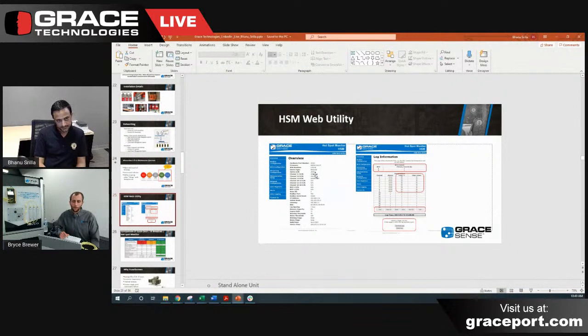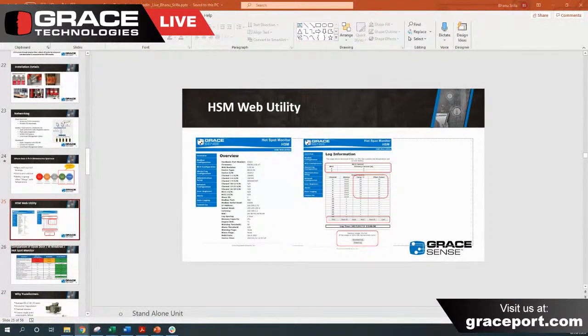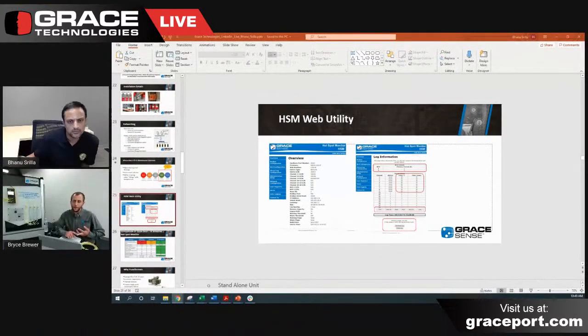Yeah, absolutely. So the way you would set up one of these devices is you can plug in right from your computer using an Ethernet cable and bring up the HSM web utility you're seeing there. The web utility allows you to put in IP addresses - that's where you would set that up. So it's kind of a tangent from what Banu was saying, but this is where you configure your IP address. For a standalone setup, you can go in and set your alarm thresholds.